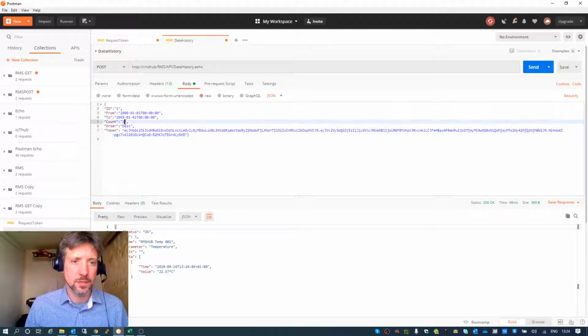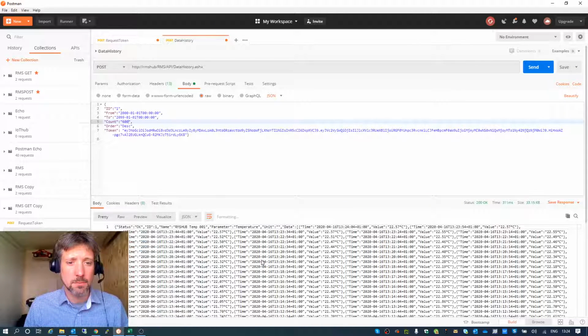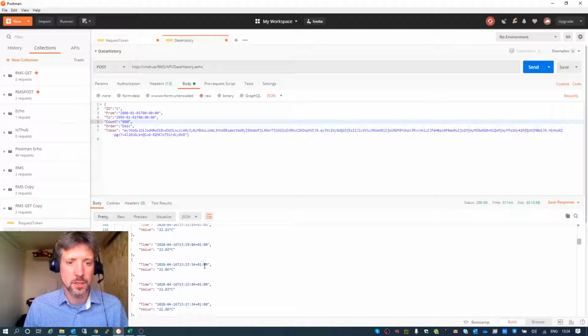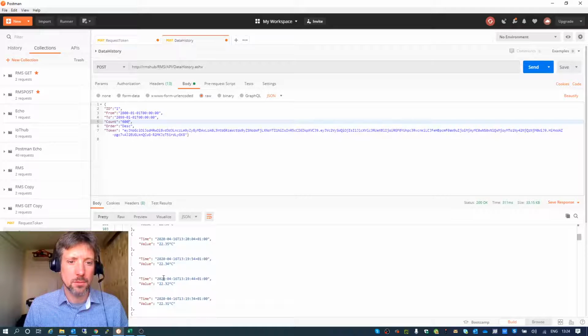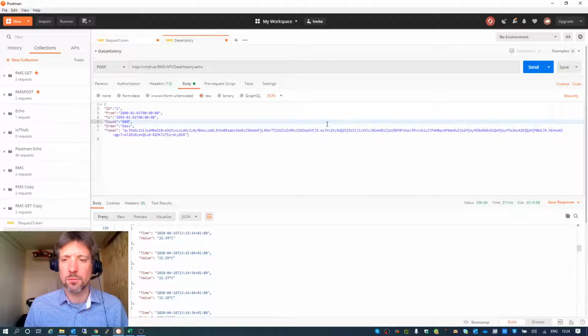If I wanted to have loads of readings, then obviously I just put in the count there, and that'll download the last hour of data there, 10 minute log interval, so you can see all the readings there slowly creeping up as the weather warms up.